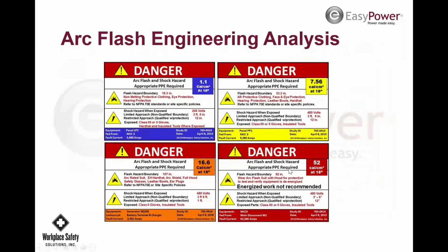So here's our colors. Our green color is generic low, and then the blue is generally, this is actually a low level, 18.3 inches, 1.1 calories. So it's just non-melting clothing, eye protection. And so if you go over here, once you get over 4, it goes to yellow. And this tells you the calorie rating, the distance, the PPE requirements.